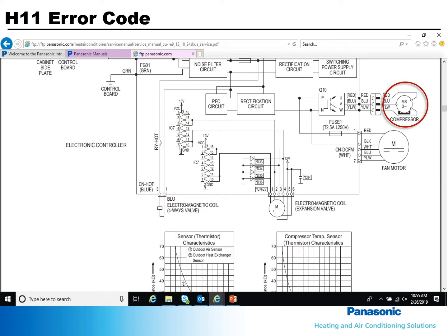Unplug the compressor and verify it is not open or shorted. To 100% know if a compressor's windings are good, you need to use a megohmmeter. Unplug and ohm the fan motor. Unplug and ohm the reversing valve coil.